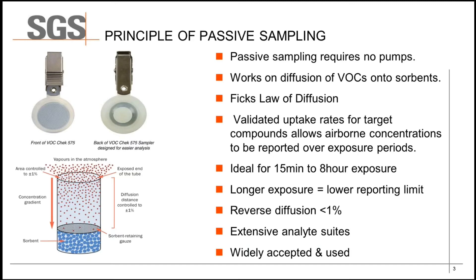Passive samplers are ideal for long-term exposure. Samplers designed for workplace health assessments are ideal for 15 minutes to an 8-hour exposure. Passive samplers designed for environmental monitoring applications can be deployed for much longer, and some environmental samplers have been validated for up to a 30-day deployment. To sample for such an extended period of time, these samplers must overcome moisture in the atmosphere. Sorbents such as charcoal will readily absorb moisture, and uptake of moisture deactivates the sorbent if it is hydrophilic. For long-term monitoring, effects of moisture are combated by selecting sorbents that are hydrophobic, or using membranes that are impervious to water but allow VOCs to pass through.